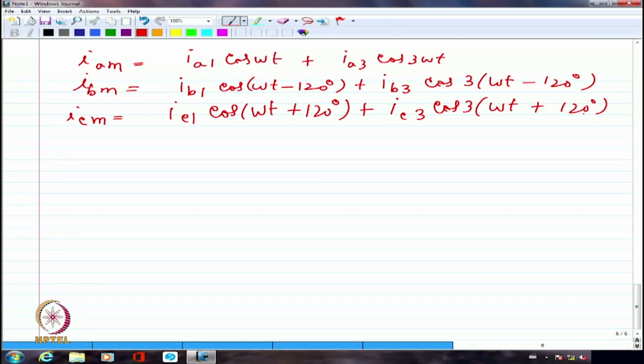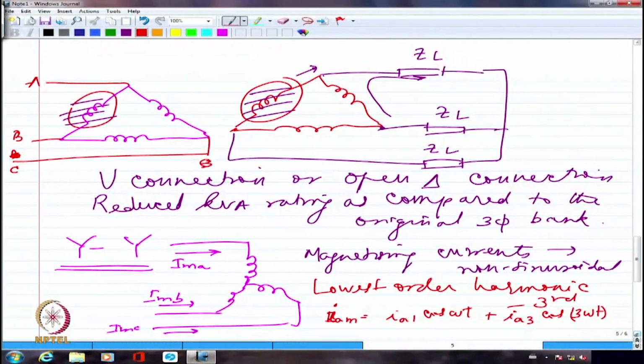Now, when I look at the star connected system, I have iMA, iMB, and iMC, and the neutral is not connected. So iMA plus iMB plus iMC equal to zero is fine. If iMA plus iMB plus iMC is not equal to zero, I have to provide a path—connecting the neutral to ground or somewhere. If I don't connect the neutral, the third harmonic cannot exist.